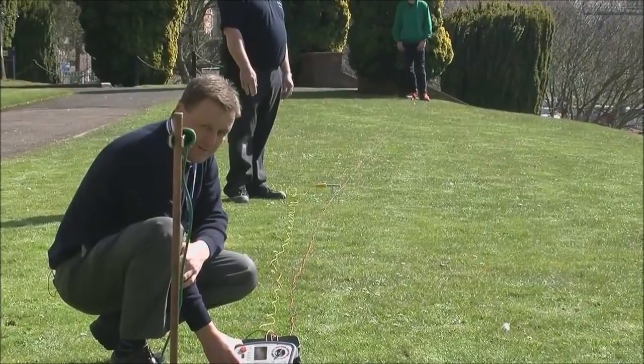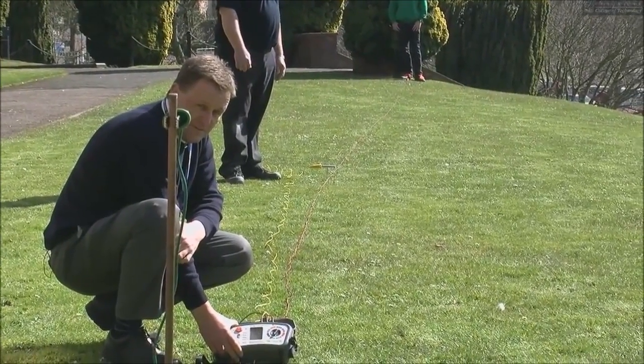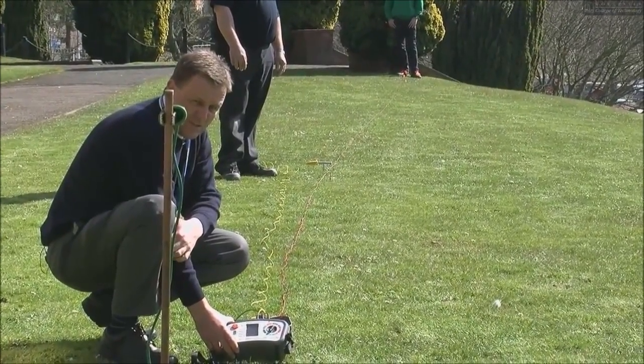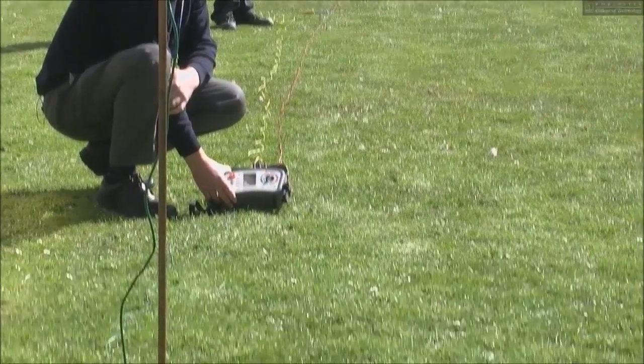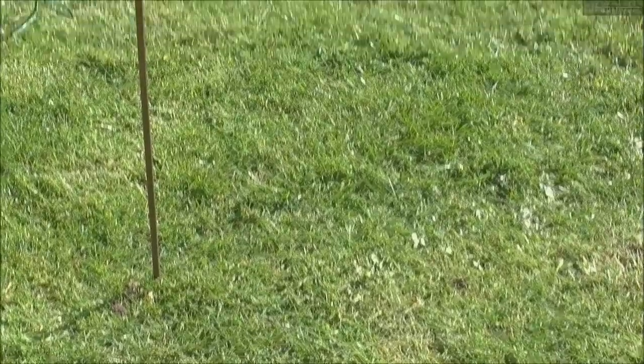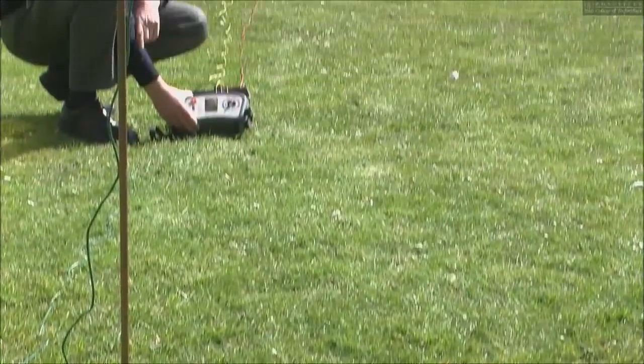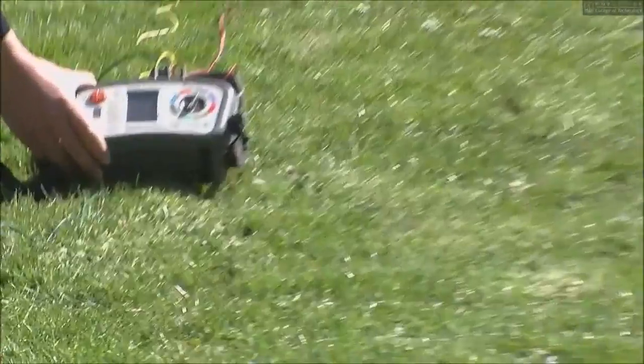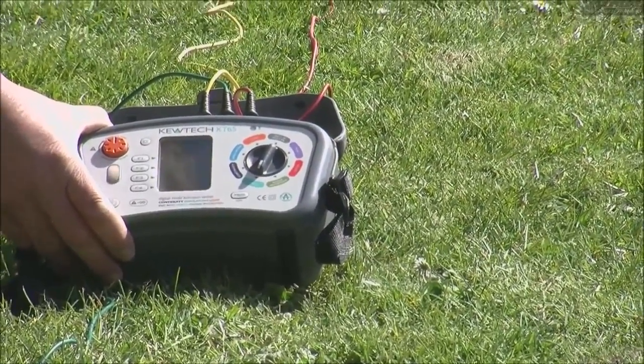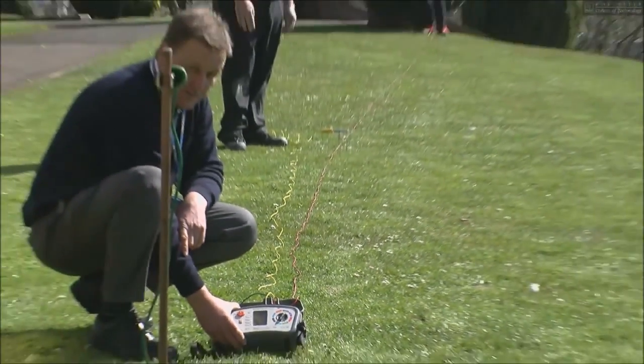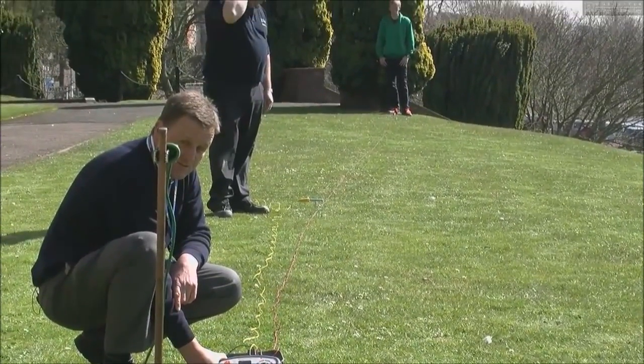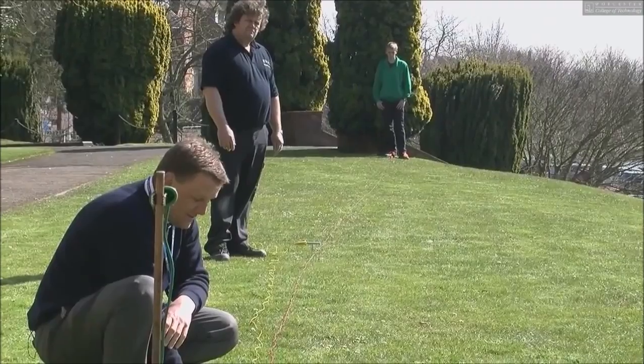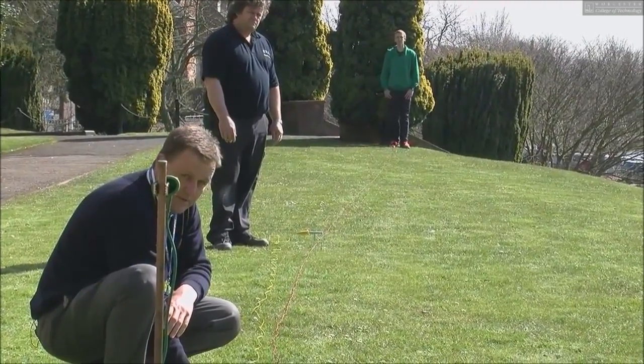As you see, we have the earth electrode just placed a couple of inches into the ground at the moment, and the cables are run out in a dead straight line. And as you can see on the tester, we have 665 ohms, which isn't really acceptable, but the earth electrode hasn't been hammered into its full capacity yet, so we should expect that reading to come down.